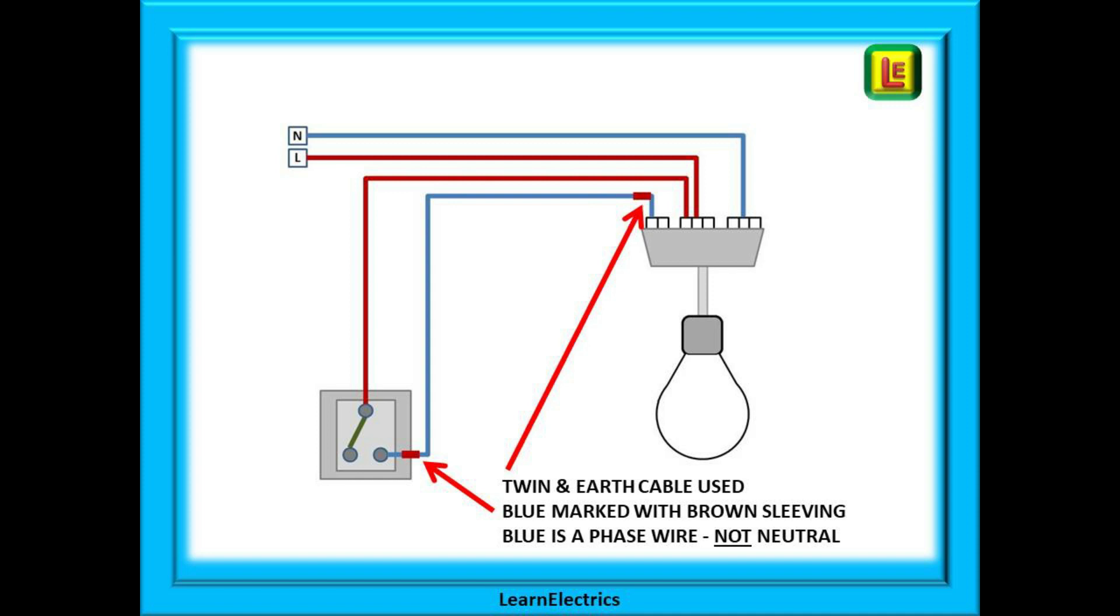One important piece of safety advice. We are using standard twin and earth cable to connect between the ceiling rose and the switch. This means that the blue wire that returns from the switch to the ceiling rose is not neutral. It is not neutral. It is a phase wire and it can have 230 volts on it.